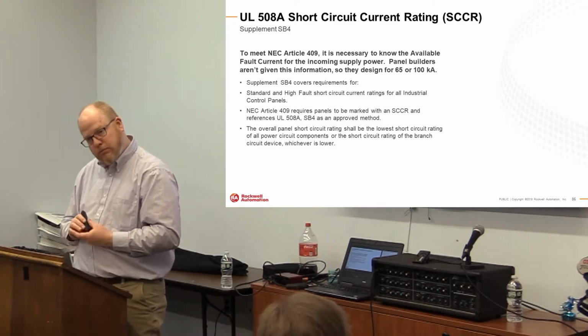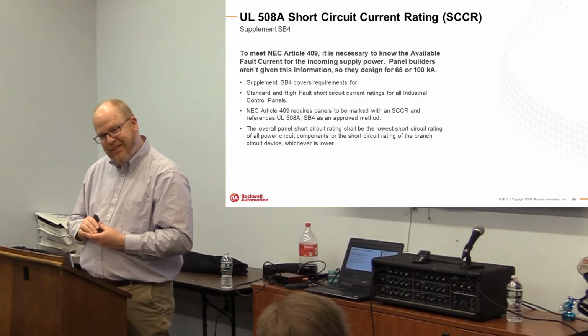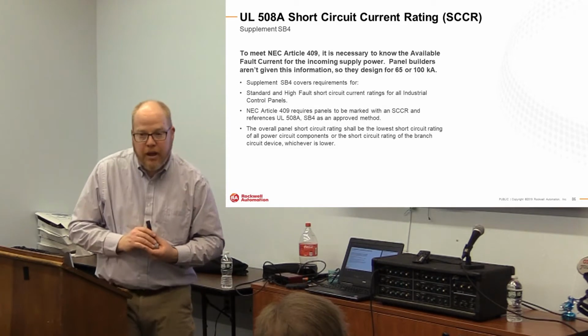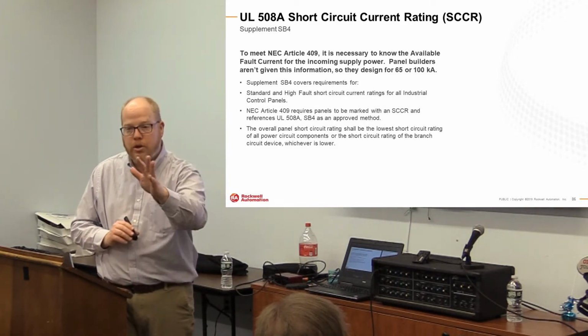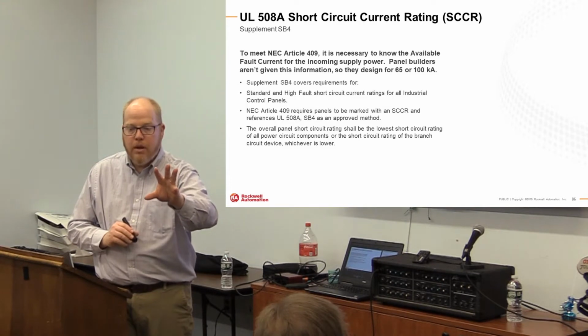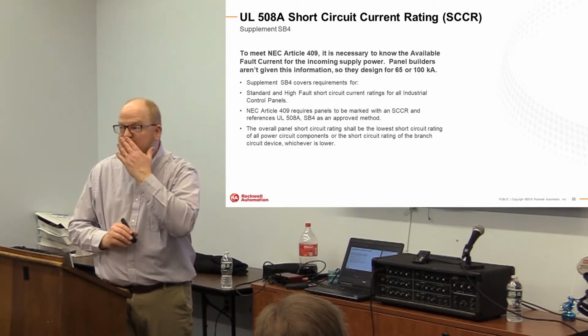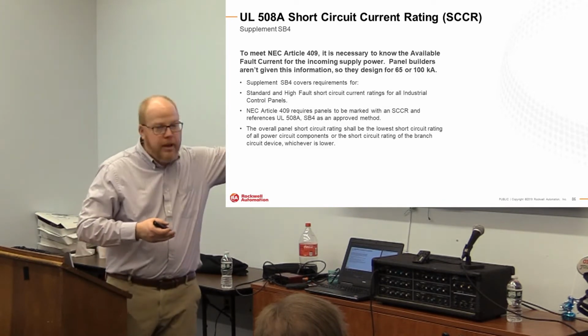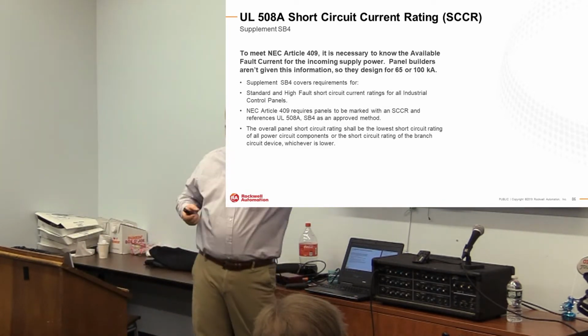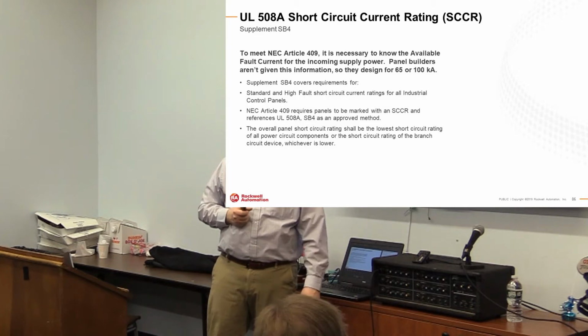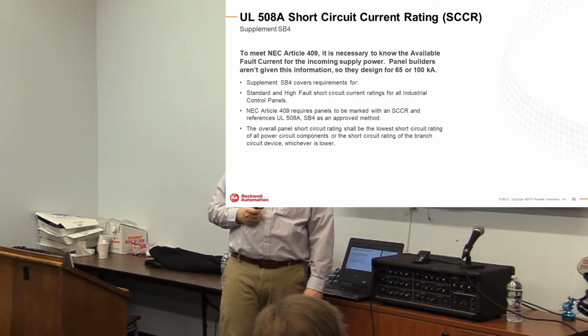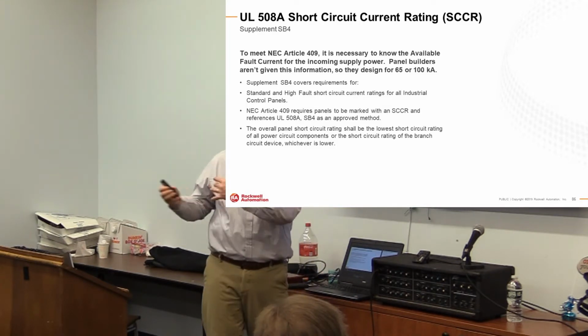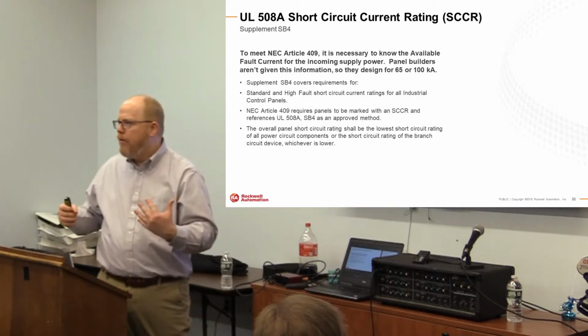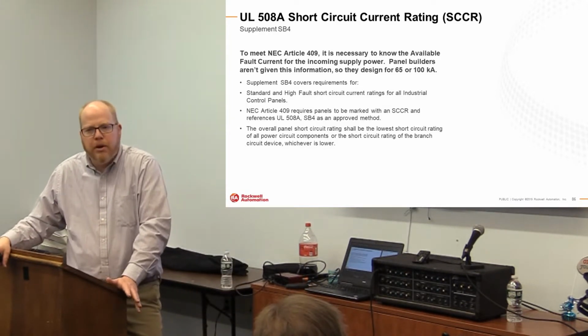So when you're not given that information, how do you do the calculation? Well, you don't need the available fault for the calculation. Your user does for their NFPA 70E stuff. Basically what they will do is prescribe a peanut butter. Like they'll say, oh, just give me 65. And then you label it 65 and they'll make sure it doesn't get attached to anything less than that, is what they'll say. But quite frankly, 65 is overkill. There are many cases where you won't get anything over 25. But you don't know that. They don't know that, so they'll prescribe a very heavy short circuit current rating requirement. It's the peanut butter engineering approach.